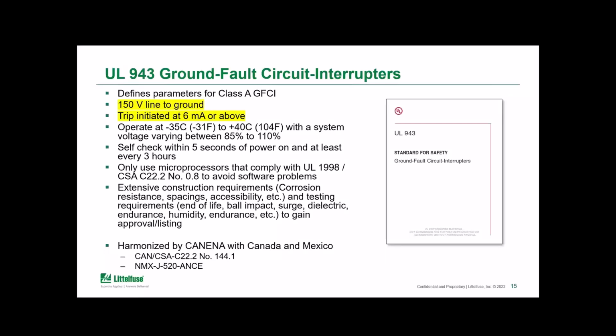The main points to remember here for a Class A GFCI are a 150 volt line to ground device with a 6 milliamp trip. Now, just as a side note, technically the standard says it must trip at currents of 6 milliamps or higher and must not trip on currents 4 milliamps or lower, or even 3.5 milliamps and lower if the ambient air is less than 23 degrees Fahrenheit or more than 104 degrees Fahrenheit.